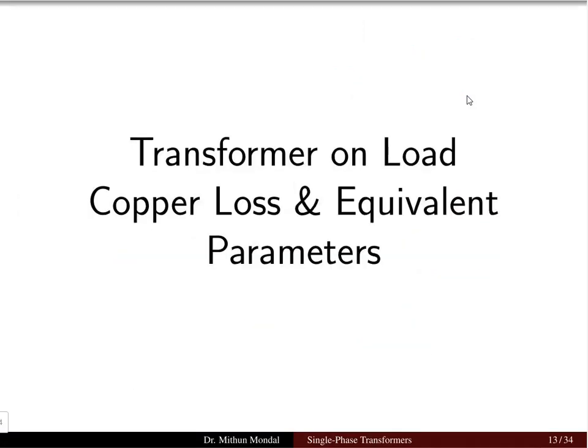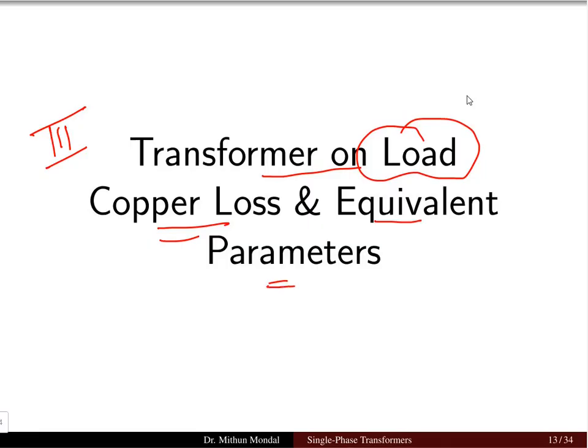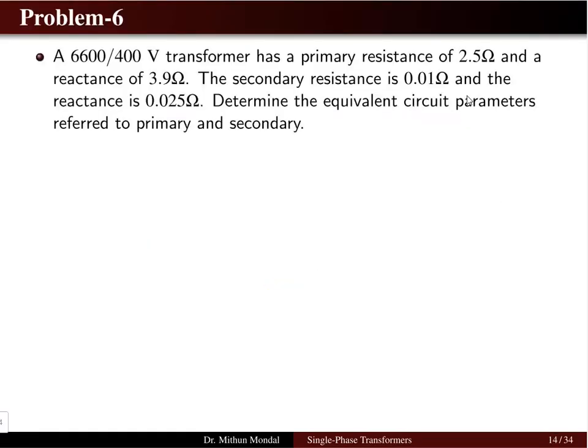The third part of the transformer fundamentals we will take is the transformer on load. When the transformer is on load, copper losses will be there, and we have to obtain the equivalent circuit parameters of the transformer. So let us see problem number 6, where we have a 6600 by 400 volt transformer. The primary resistance R1 is given as 2.5 ohms, and the reactance on the primary side, X1, is also given as 3.9 ohms. The secondary resistance R2 and the secondary reactance X2 are given. Determine the equivalent circuit parameters referred to the primary side and the secondary side.